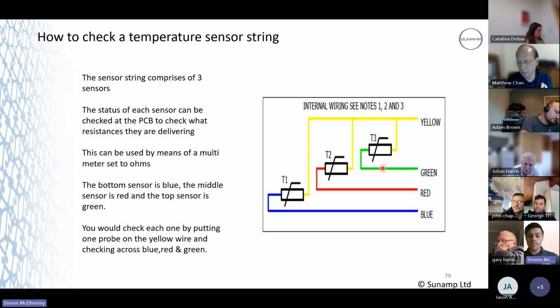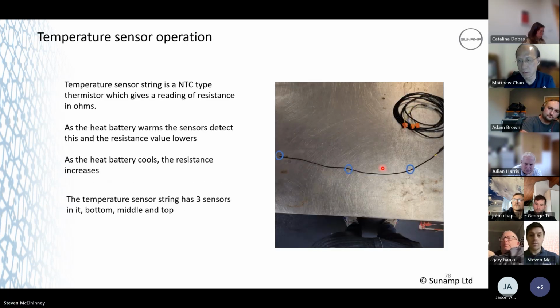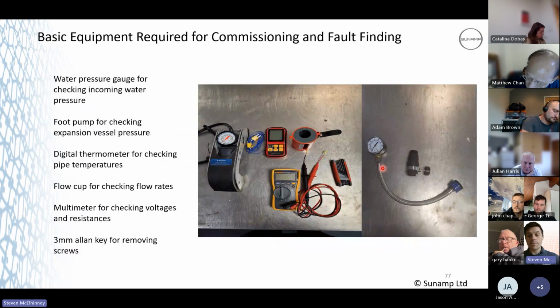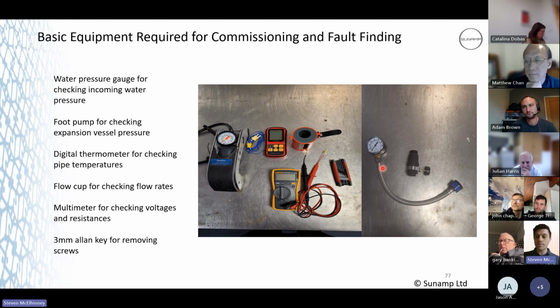Part of your commissioning, maybe what you should have in here is a current clamp as well, because once you're commissioning it, unless you can see what's going on inside the battery, it just looks like a box with lights on it. You can get your current clamp, check your element live, and make sure the current's flowing, so you know that the unit's generating heat.